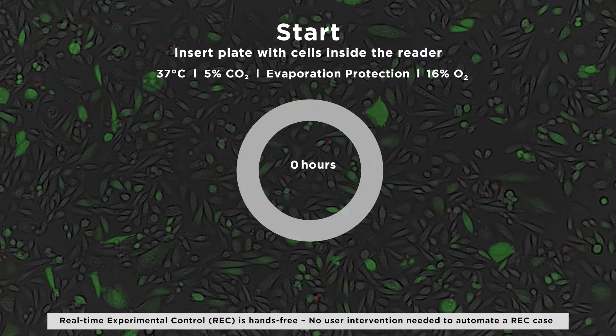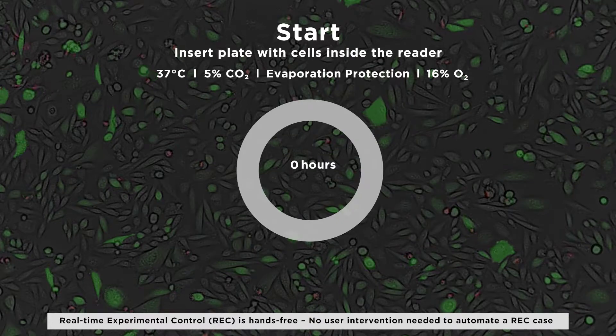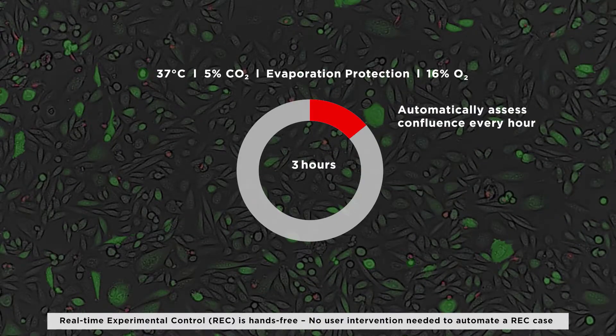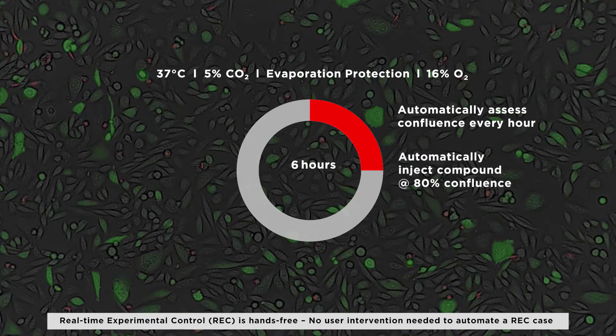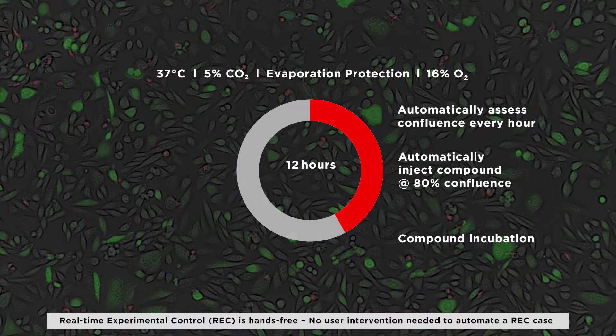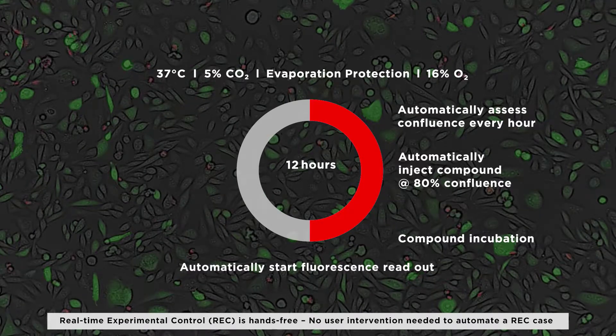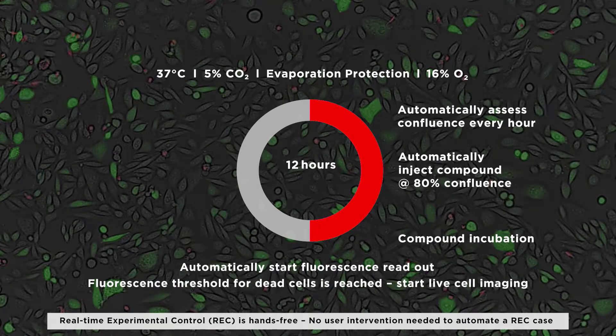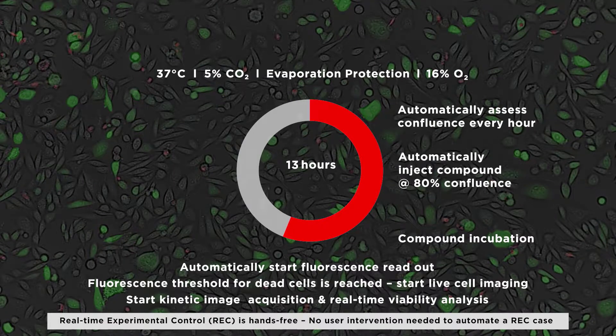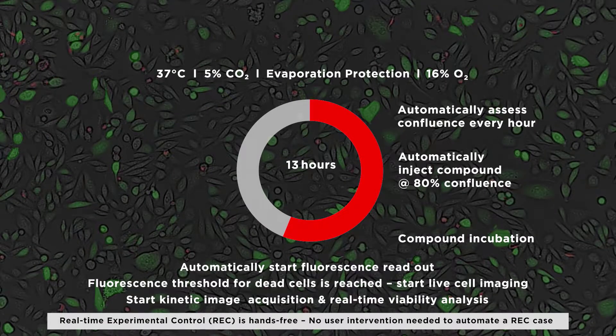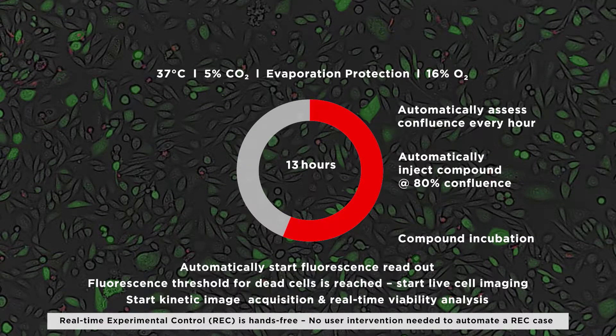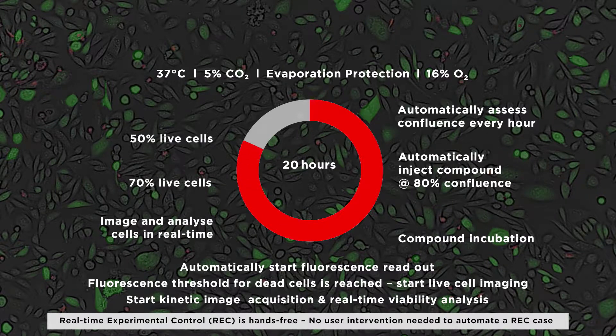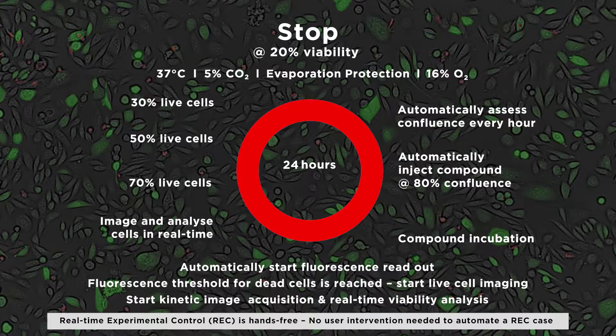To start, insert plate with cells inside the reader, assess confluence, inject compound, incubate compound, start fluorescence readout, start live cell imaging, start kinetic image acquisition and real-time viability analysis, image and analyze cells in real time, and finish when 30% live cells is reached.